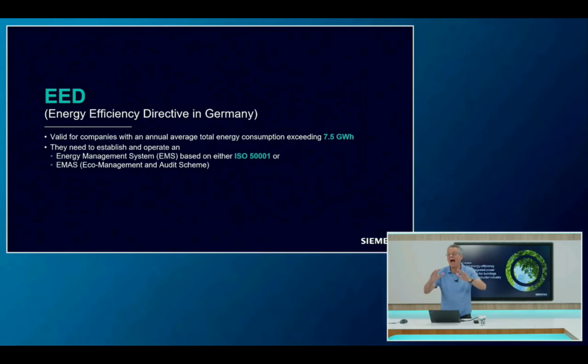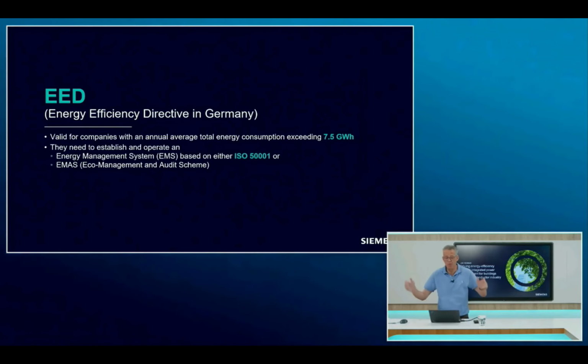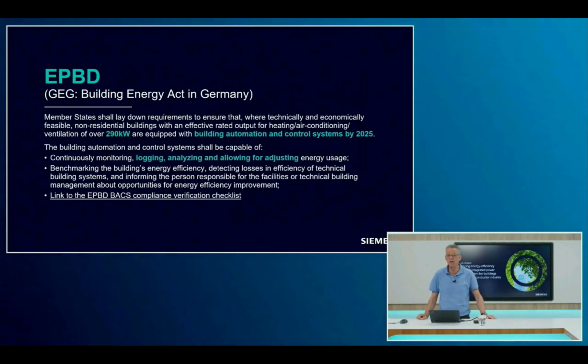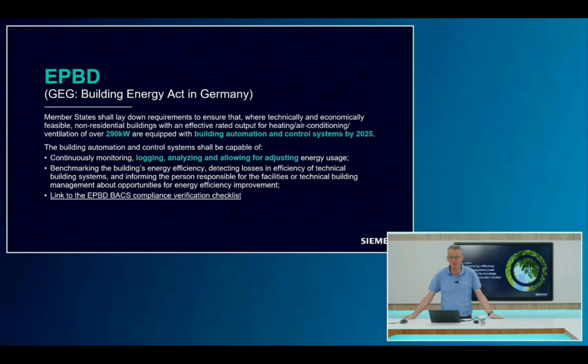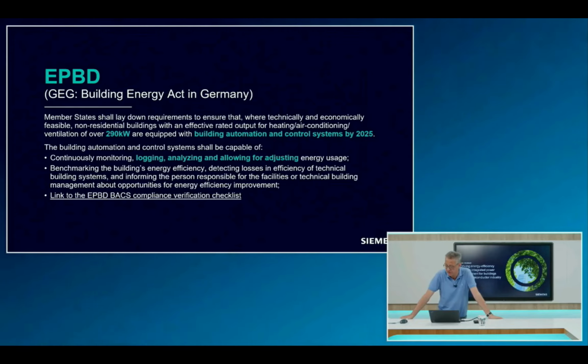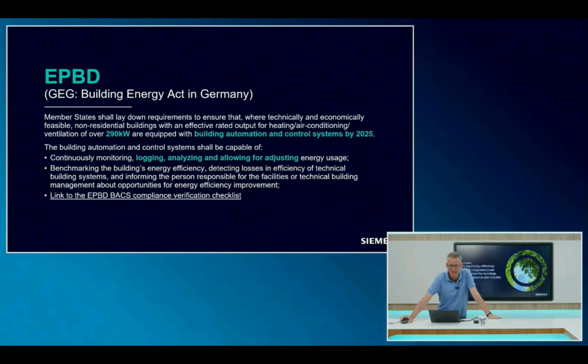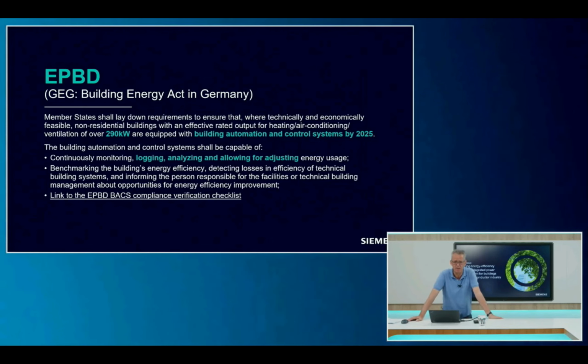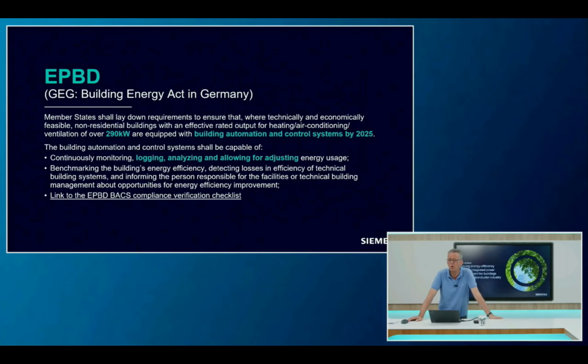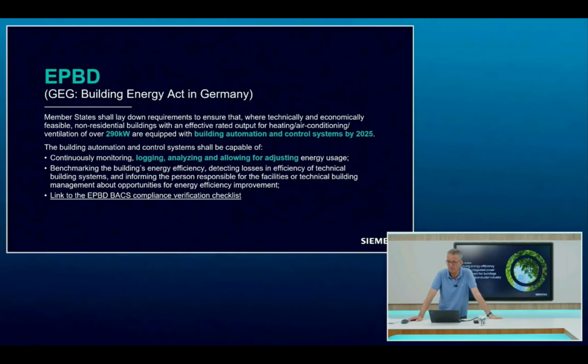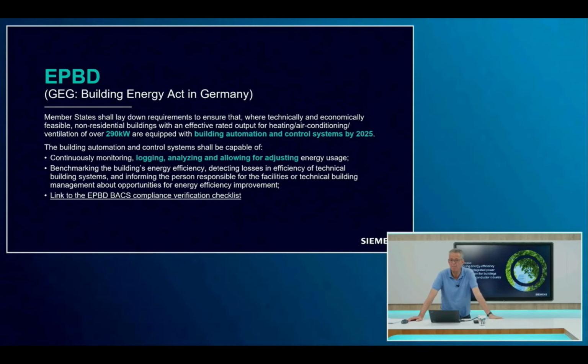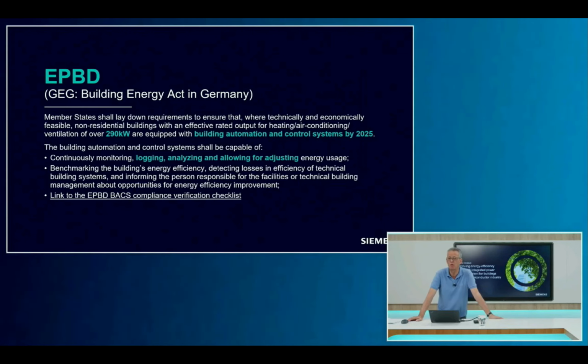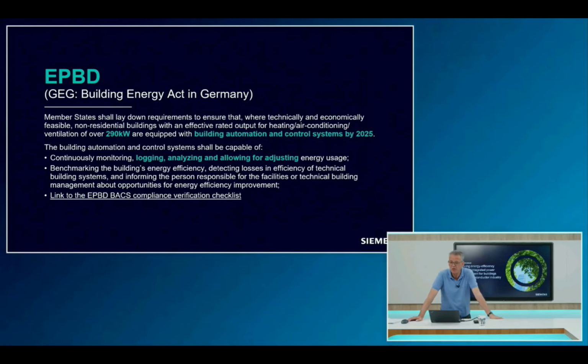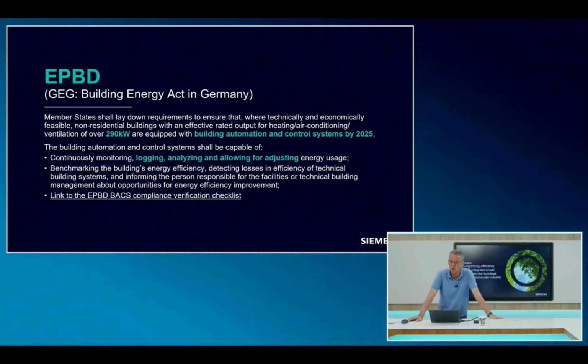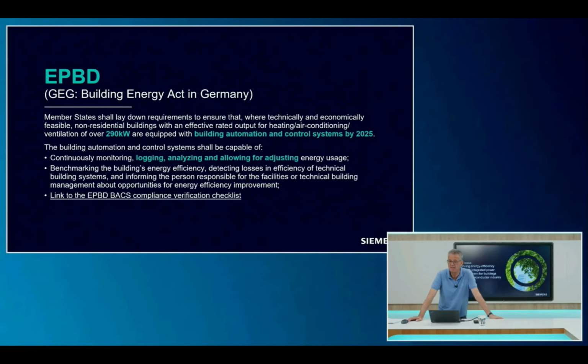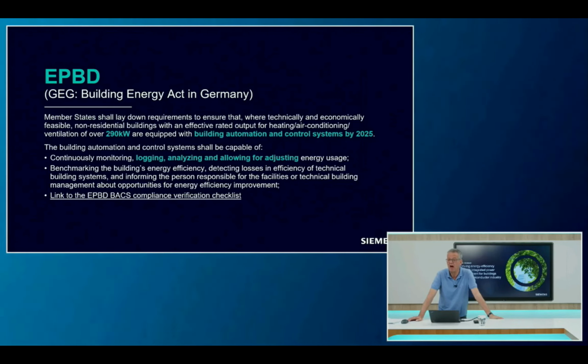That's the high consumer side, the gigawatt hours. Now let's go back to heating and cooling, which is more the megawatt hours. Here we also have some relevant triggers. If a building has an installed power for heating and cooling equipment of 290 kilowatts or more, it must have a building automation system, so it cannot be controlled manually. With this building automation system, it must be possible to monitor, log, and analyze the energy and other usages.